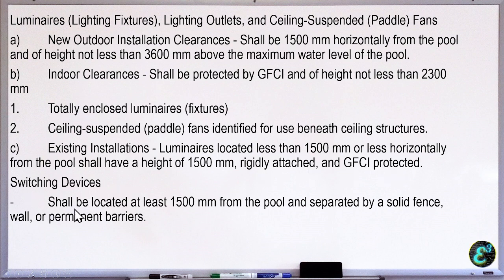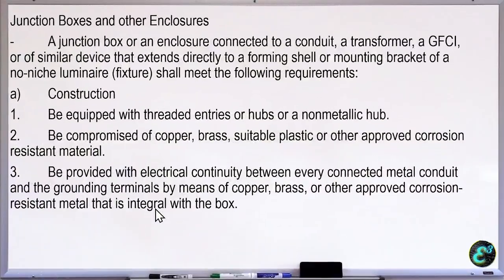So, switching devices. All switching devices shall be located at least 1,500 mm from the pool and separated by a solid fence or a wall or a permanent barrier. No? So, pinaka-common na clearance dito is 1,500 mm. So, junction box and other enclosures sa ating pool. So, dapat junction box are connected to a conduit and a transformer at dapat may GFCI or similar device that extends directly to the forming shell. No? So, ito yung kanyang mga requirements.